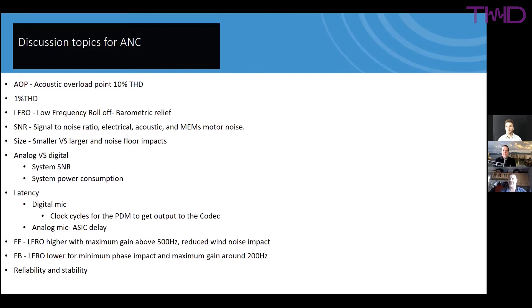Improving performance with lower LFROs introduces manufacturing difficulties. When producing 17 million microphones per day, even simple problems become enormous — including how to test them, what the settling time is, and how to measure sensitivity at low frequencies, since low frequencies require more settling time.